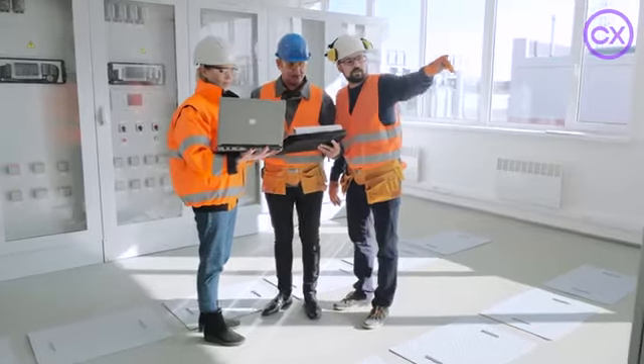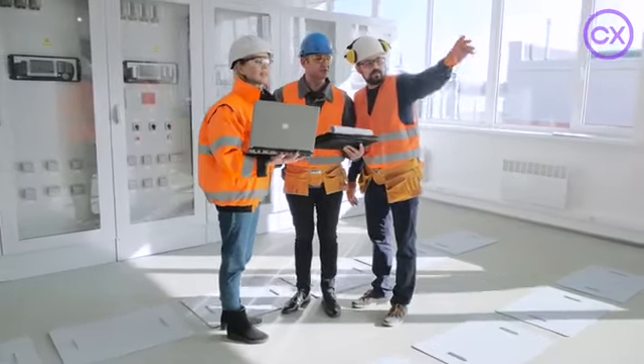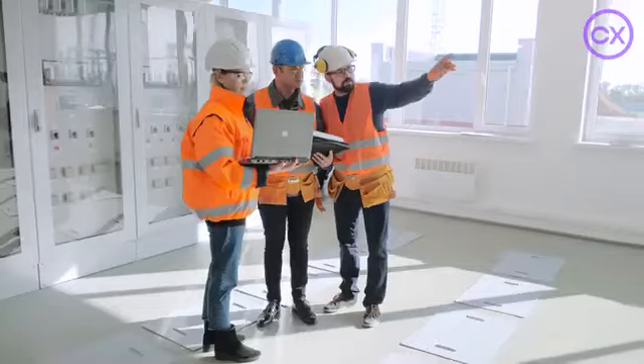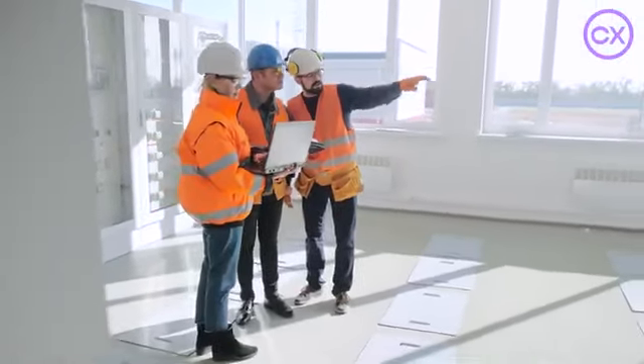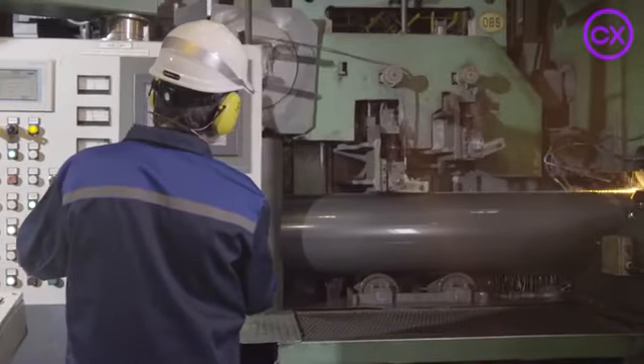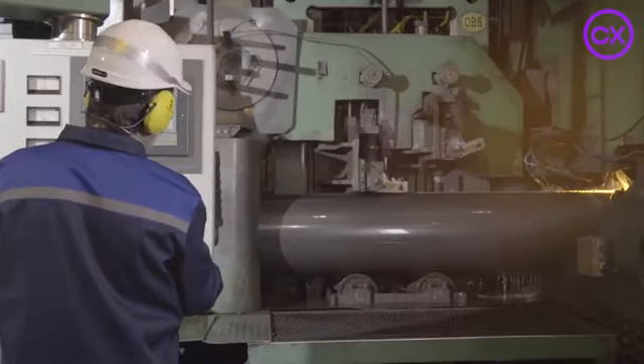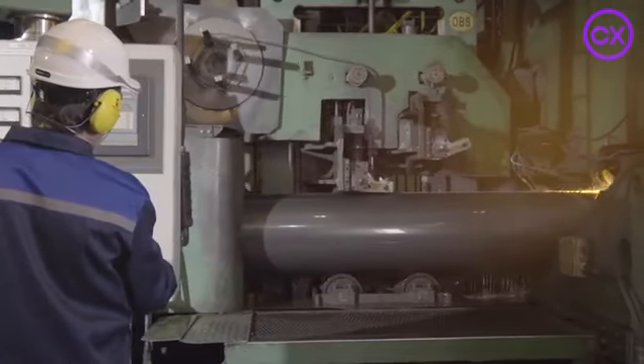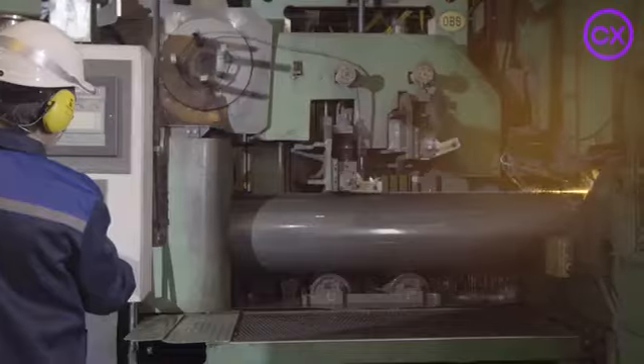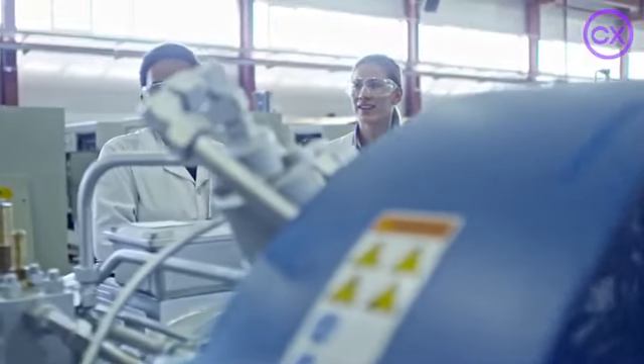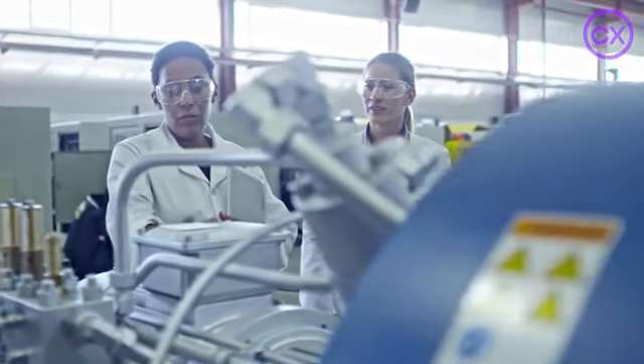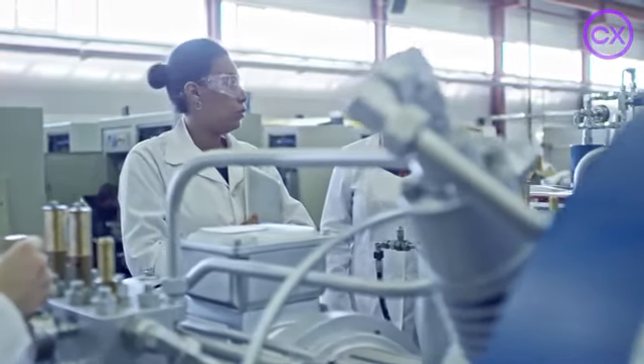Pre-commissioning is also known as vendor startup, since each vendor's equipment is started for the first time on site to confirm function of each piece of equipment. Following pre-commissioning, we can now move into commissioning tests. Commissioning involves testing multiple pieces of equipment together to function as one system. For example, a chemical dosing skid is made up of pumps, piping, valves, pressure gauges, flow meters, VFDs, and a PLC controller. During commissioning, all of these components are tested together as one system, integrated as a chemical dosing system.